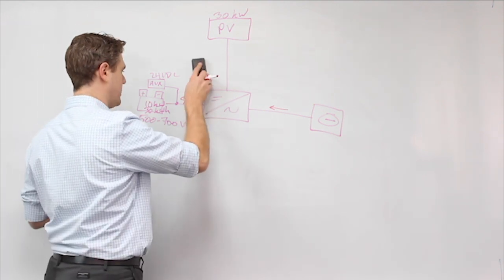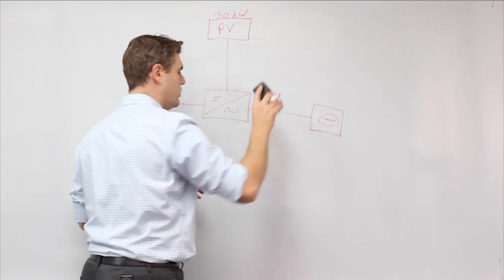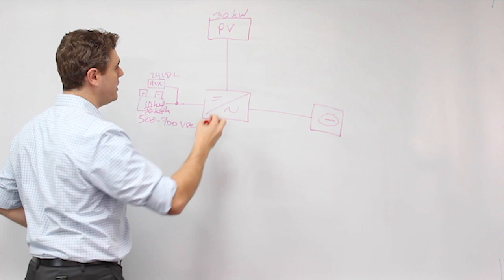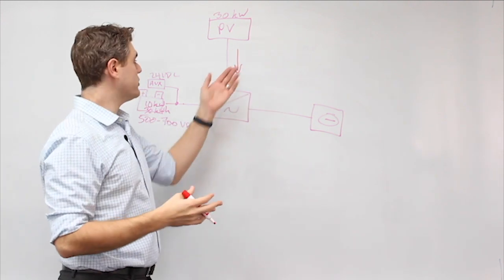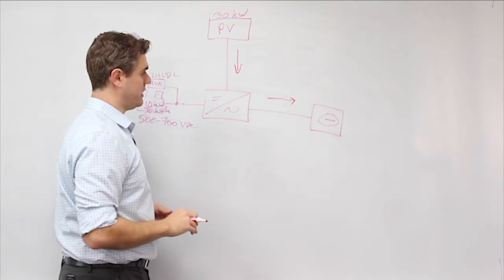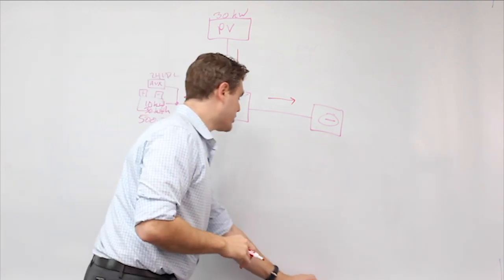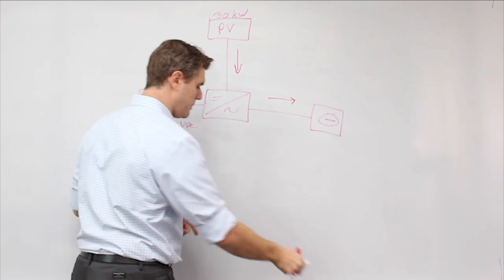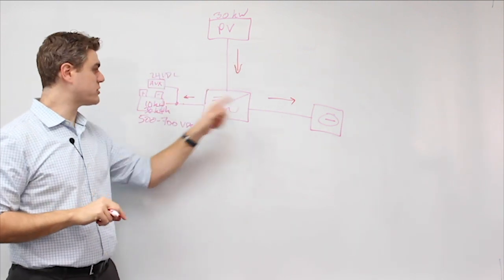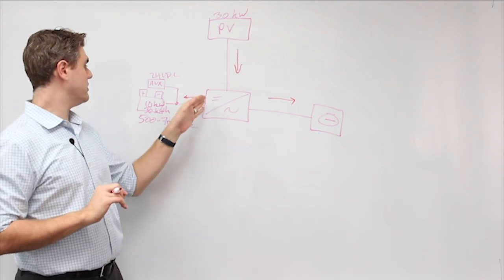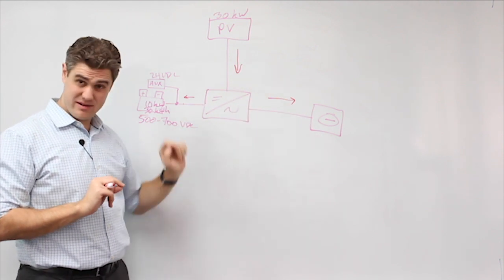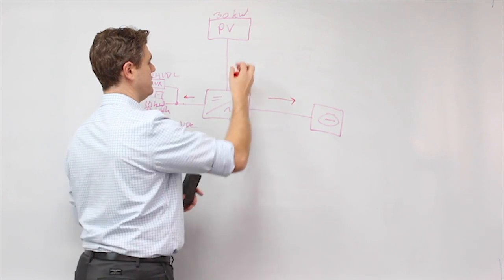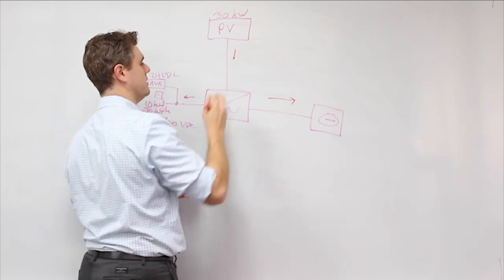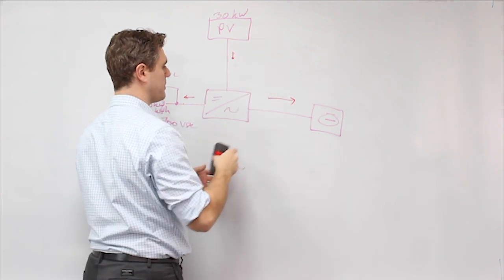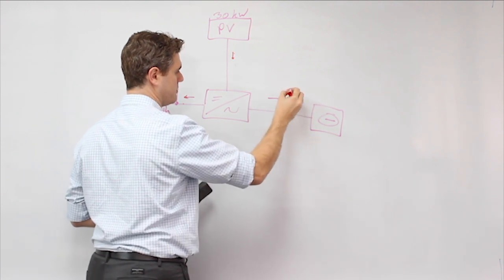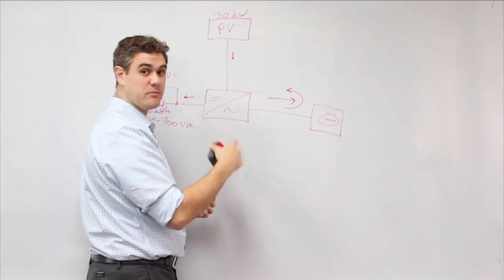The way non-import works is we are going to propose that in the beginning of an average day, the solar is going to be generating a lot, which means most of it is going to be exporting. And let's say, again, since we want to show that we will never import from the grid, we're going to show this battery charging, and how we're going to prevent it from charging from the grid. So this is the worst case scenario, right? We've got the battery charging, we've got some energy going out, but now it's sunset. The sun's going down. This arrow gets a little smaller, and a little smaller, and a little smaller, until eventually this guy flips. And now energy is coming from the grid.